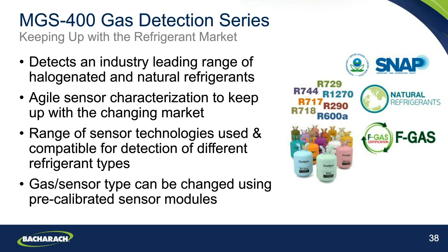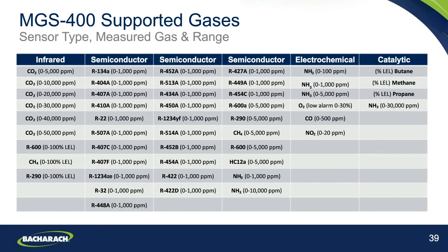And of course, we can say with the MGS-400 series that even if you were to update your system to be using a new drop-in gas from one of the newer refrigerants to the market, it's very easy to just update the detection system by using those pre-calibrated sensor modules to swap in and out of the system for any new gas coming to market. And on the screen here, we can see a list of the current gases that are supported by the MGS-400 platform and the technologies that those sensor types are on.